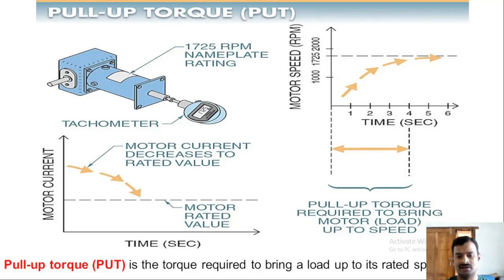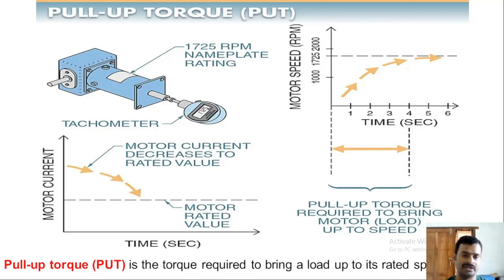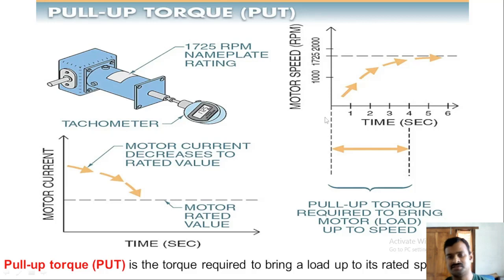Pull up torque is the torque required to bring a load up to its rated speed. For example, a motor rated at 1725 RPM connected to a load via a pulley or belt needs sufficient torque to accelerate from zero to rated speed — that is called pull up torque. On the graph, the starting inrush current is high, then slowly reduces as the motor accelerates, and the speed increases until it reaches rated speed.